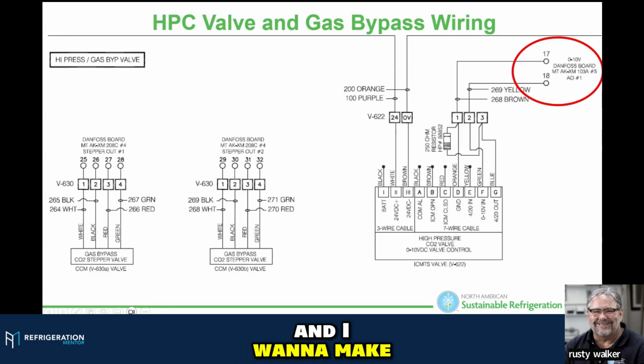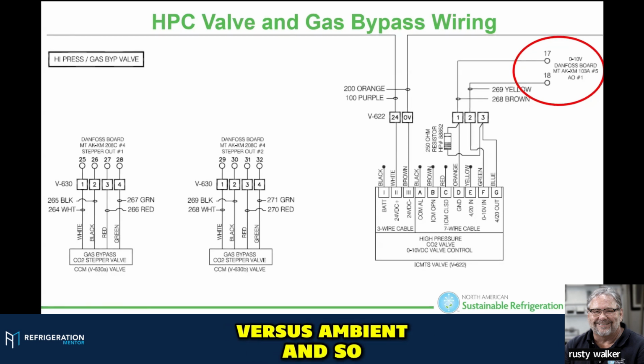And I want to make sure, because as we do boosters, we want to get in the habit of looking at where the high pressure control valve is versus ambient. And so we want to make sure we're getting a good signal. Let me caution you here, though. There's a lot of people that are not paying attention to these high pressure control valves. How many times have you heard when you're talking about computers, garbage in, garbage out, right? We hear it all the time.